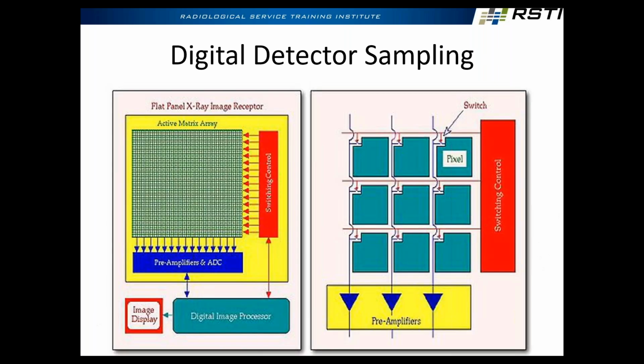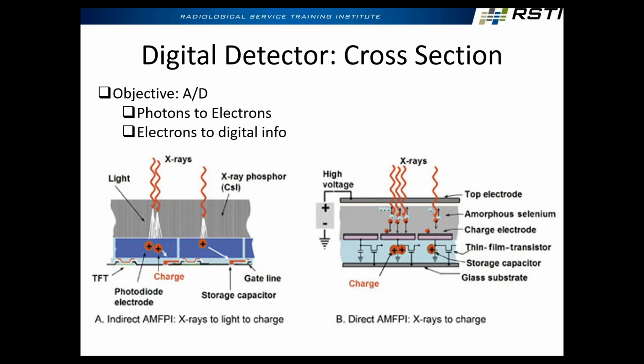So this is what a detector would look like from the top view. This is what a digital detector would look like from a cross section. And the whole objective here is to convert analog into digital. Photons are analog, and the digital is the image on the screen we want to see. That's the whole objective. But there are 2 technologies that can do this. Every digital detector out there today is either indirect or direct. What indirect means is the X-rays first get converted to light, and then that light gets read by what's called a TFT, a thin film transistor. Guess what this does?